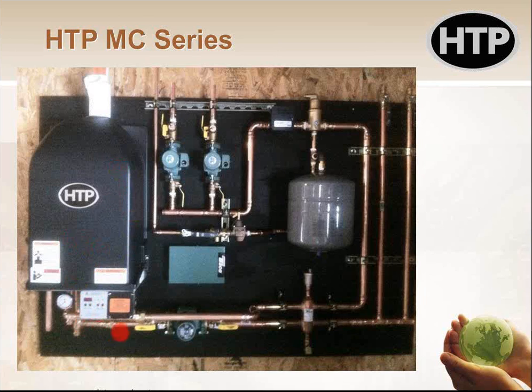So the primary loop is literally just this loop right here, where my red dot is. That's it. That's the primary loop. Over here, in this case, they have a Taco hydraulic separator, but really it could be two closely spaced T's like we talked about before. So there's my primary loop. I have two secondary loops with these two pumps here, right? So one supplies out that way, returns back around, and does his thing like that. And then his buddy next to him does the exact same thing, right? So it's pretty easy to do the primary, secondary. It's not prohibitive. You just got to do a little rework in the piping in the boiler room.